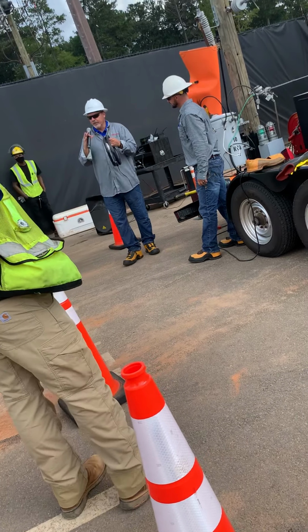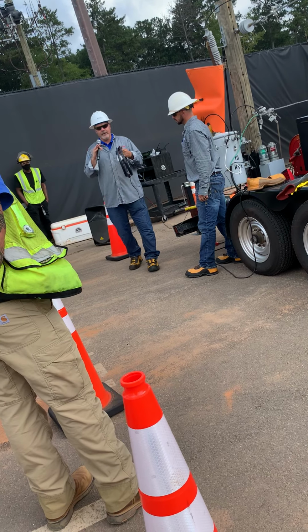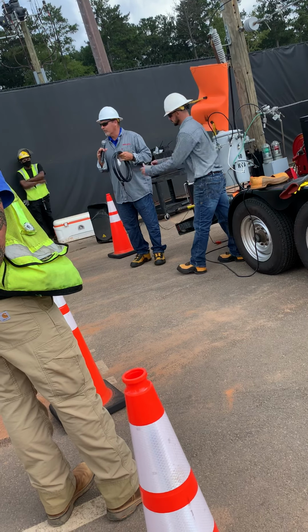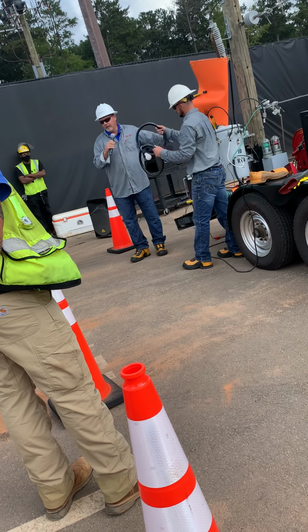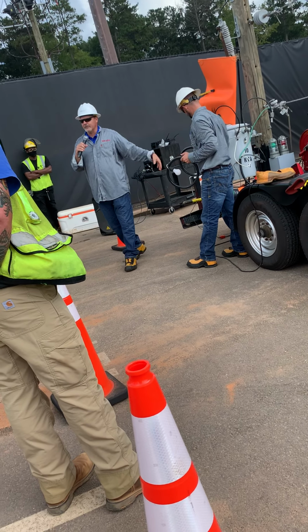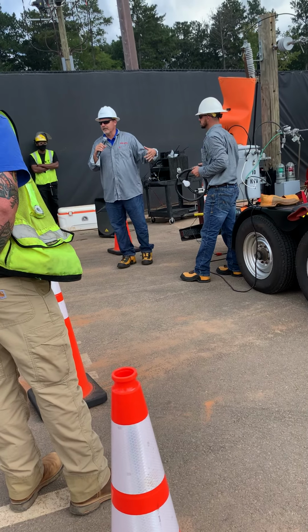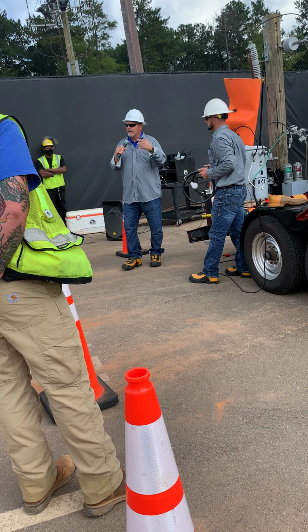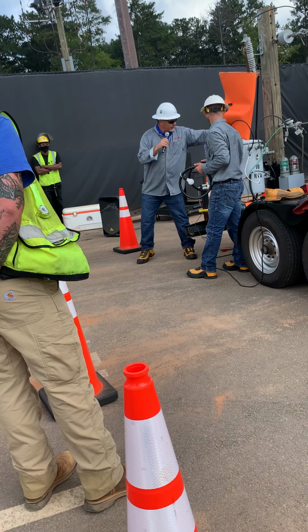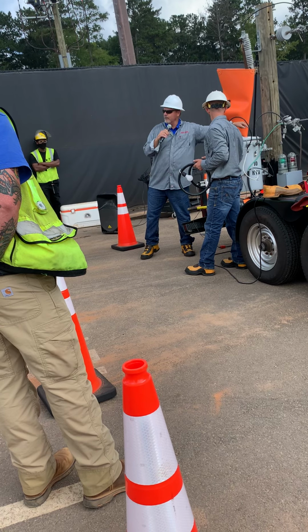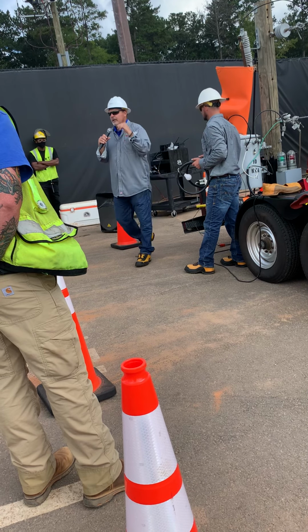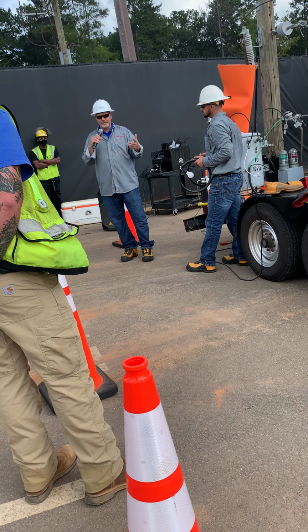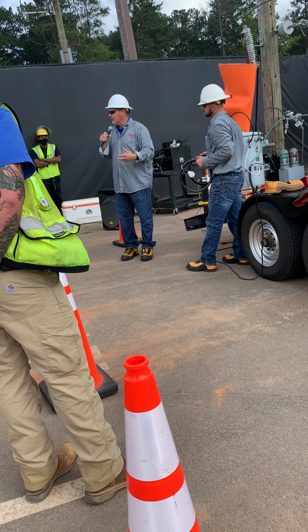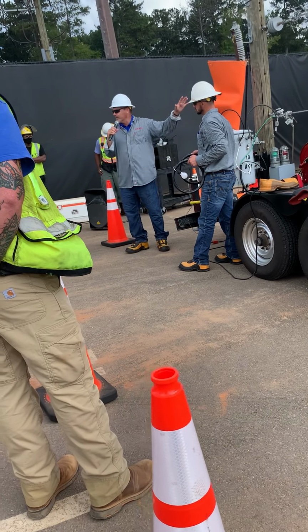A transformer works on induction, and you got a primary coil and a secondary coil. This is a 60-to-1 ratio transformer. For every 60 wraps on the primary side, you got 1 wrap on the secondary side. If we multiply 60 times 240, because we got 120 to ground, 120 to ground, across them we got 240. If we multiply that 240 times that 60, we get 14.4.